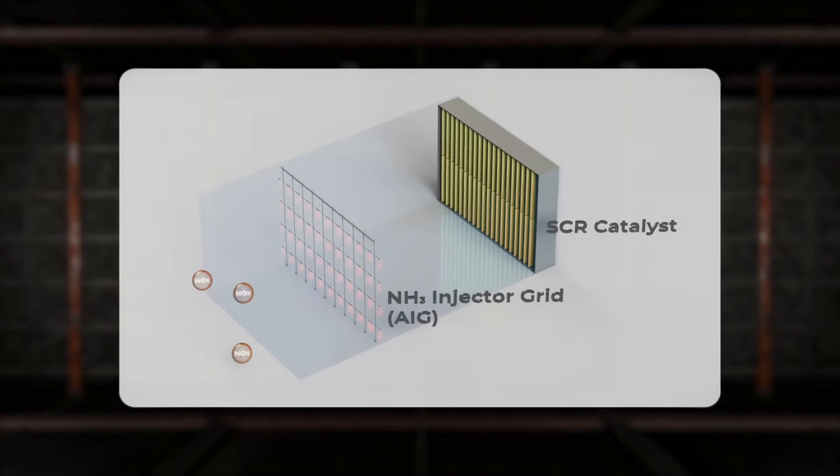However, if the face of the catalyst is fouled and the flow is disrupted, the SCR cannot reduce the NOx at the desired rate, while high SCR pressure drops may limit the output of the facility.